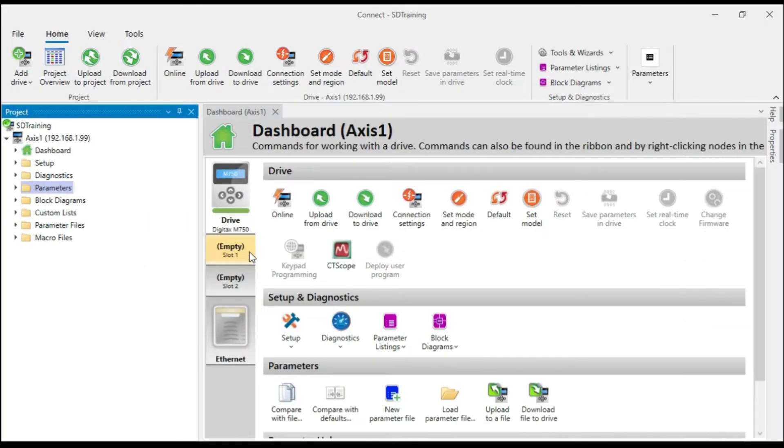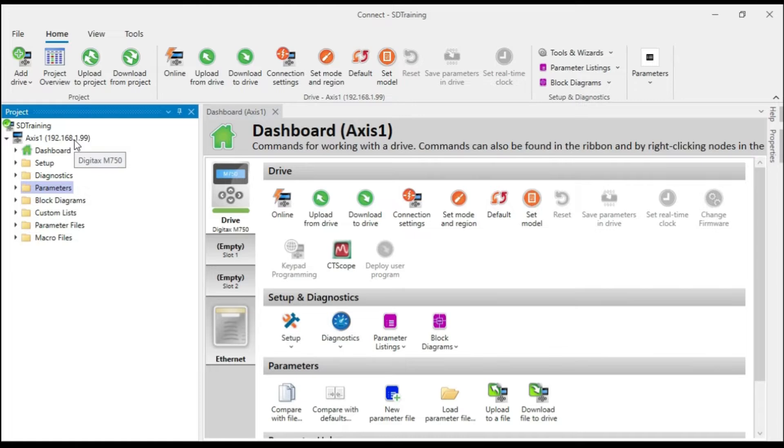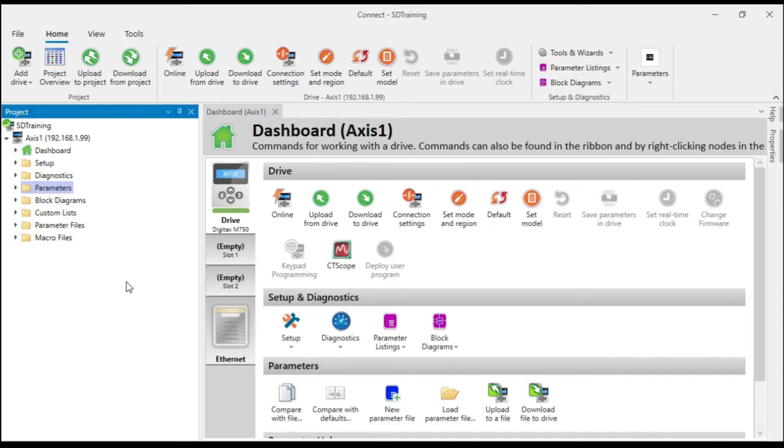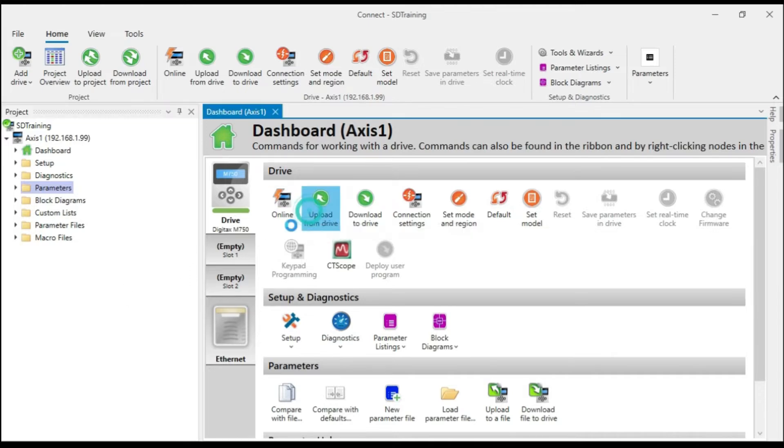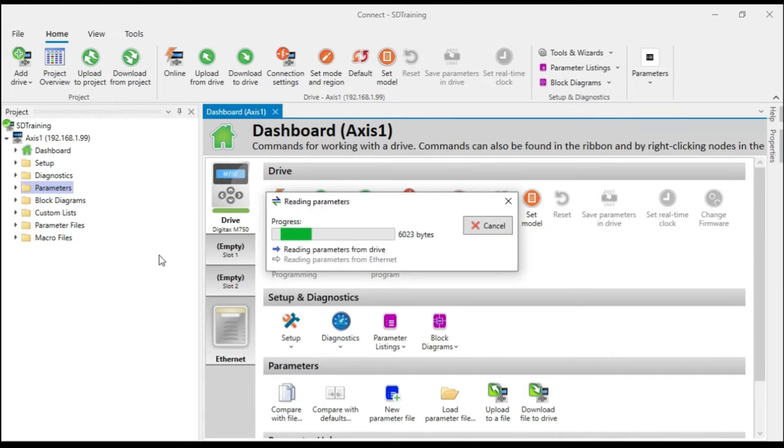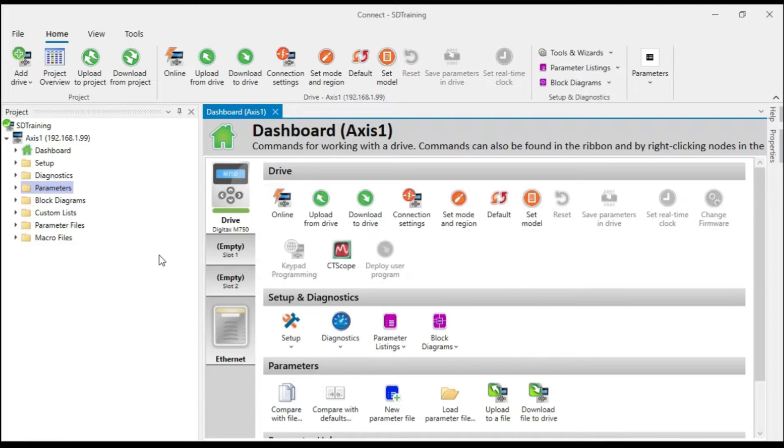I've inserted the SD card into my drive and I have a Connect project open here for that drive. So today I'm working with a Digitax M750. If I'd like to make a backup parameter set and copy that to the SD card, which is what I'm going to do, I'm going to begin by uploading the parameters from the drive I'm connected to. And what that did was that replaced my project drive parameters with the parameters from the actual drive.